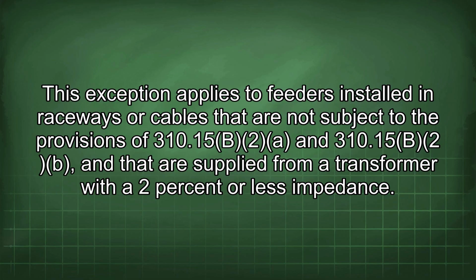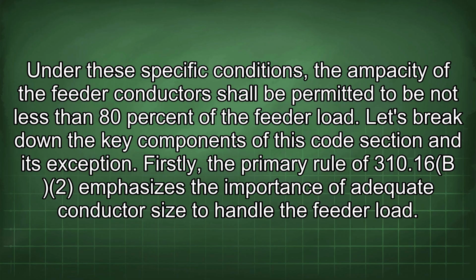This exception applies to feeders installed in raceways or cables that are not subject to the provisions of 310.15(B)(2)(a) and 310.15(B)(2)(b), and that are supplied from a transformer with a 2% or less impedance. Under these specific conditions, the ampacity of the feeder conductors shall be permitted to be not less than 80% of the feeder load. Let's break down the key components of this code section and its exception.